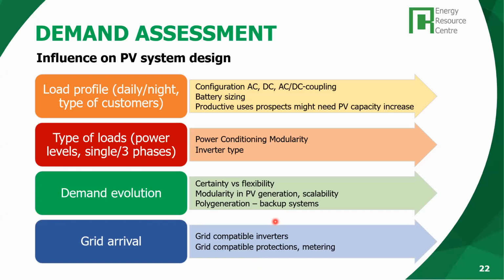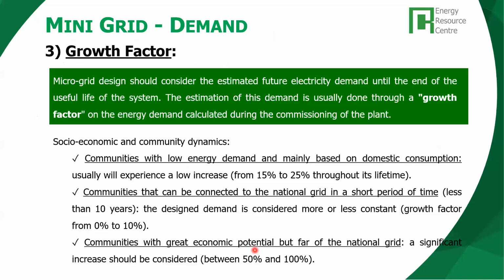So the tip is to always consider inverters, protections, meters that can be compatible with the grid. It might be a little bit more expensive when you build a mini grid, not too much, but a little bit more expensive. But it is a good design decision, because this mini grid today is off grid, but tomorrow can be grid connected. Okay, and all the investment is not wasted.